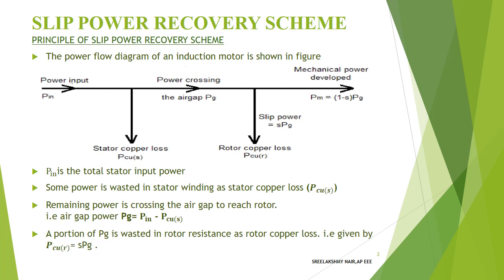Looking at the power flow diagram: the stator side receives the power input, and stator copper losses occur in the stator winding. Then we go to the air gap. Power crossing the air gap is called PG. In the rotor, the rotor copper loss occurs. The air gap power minus rotor copper loss gives the output. The rotor I²R loss represents the slip power that is wasted, denoted as S·PG.